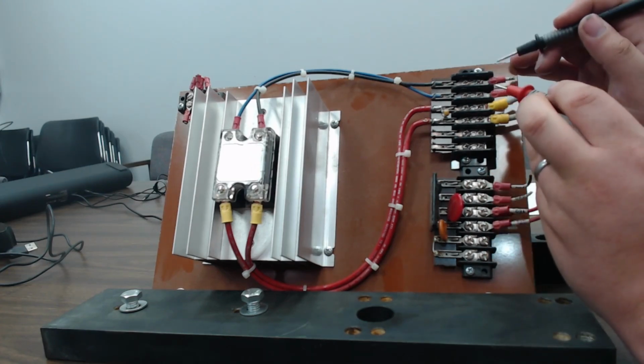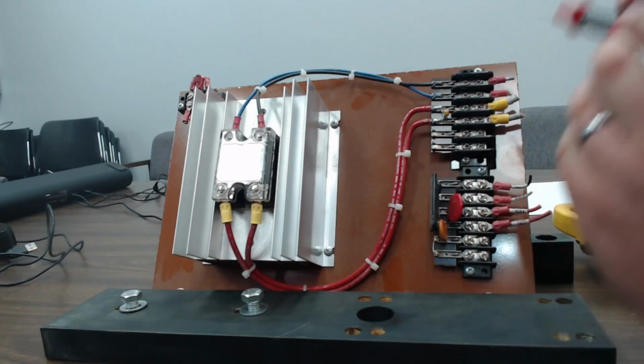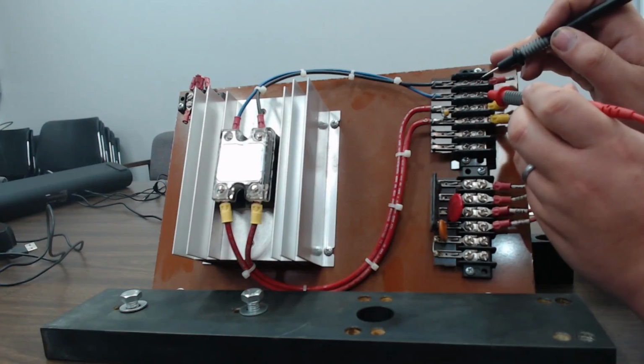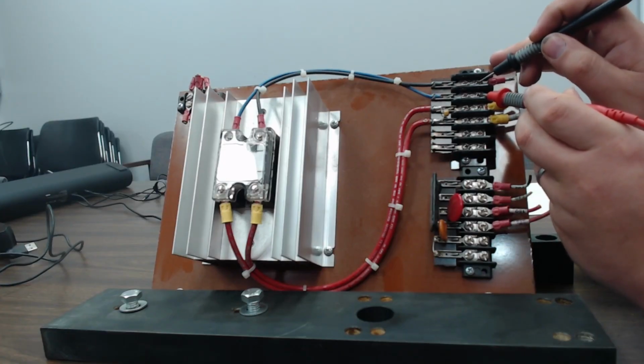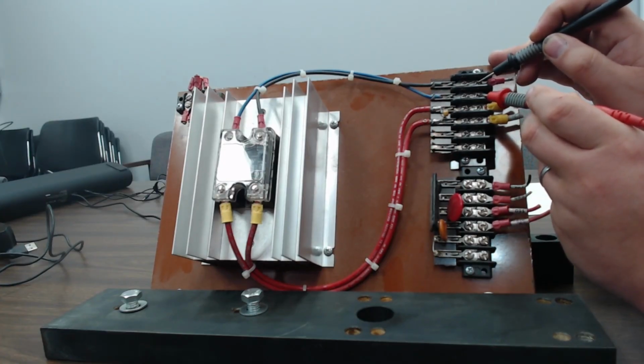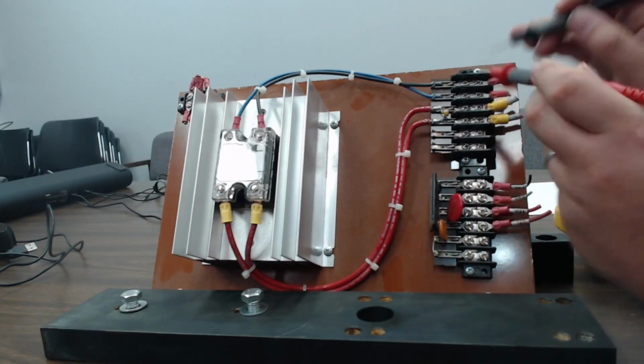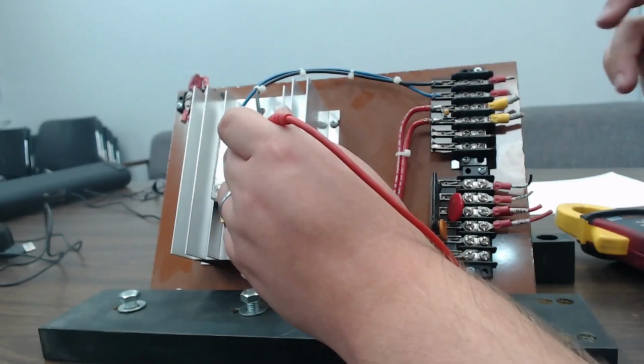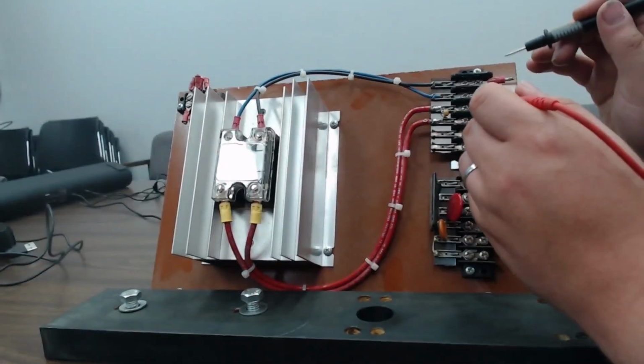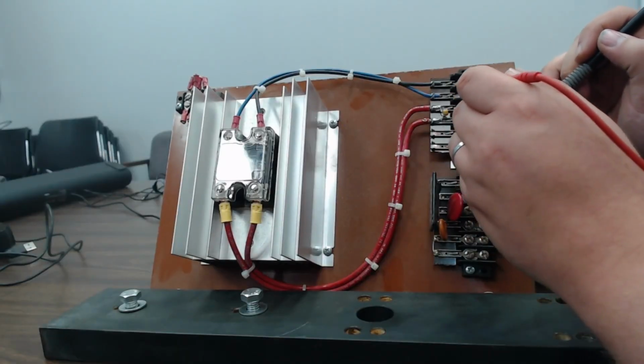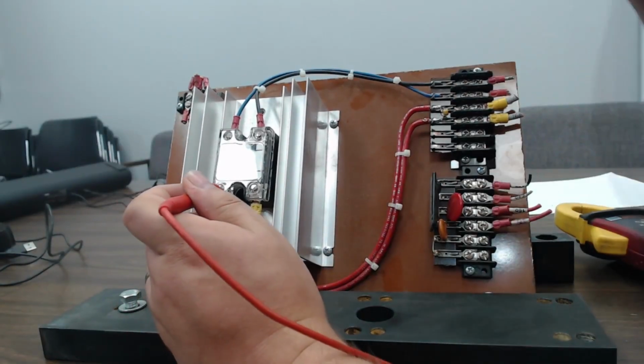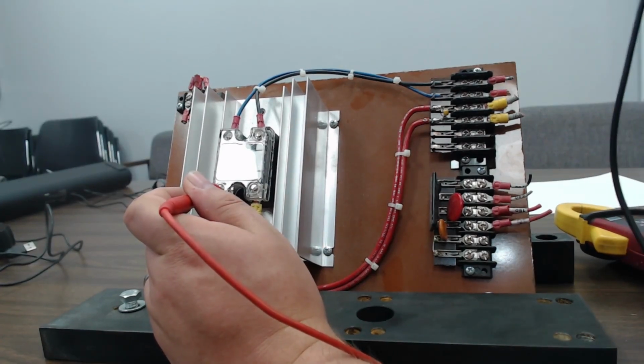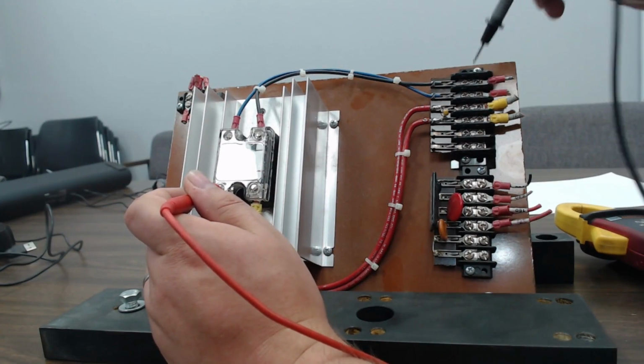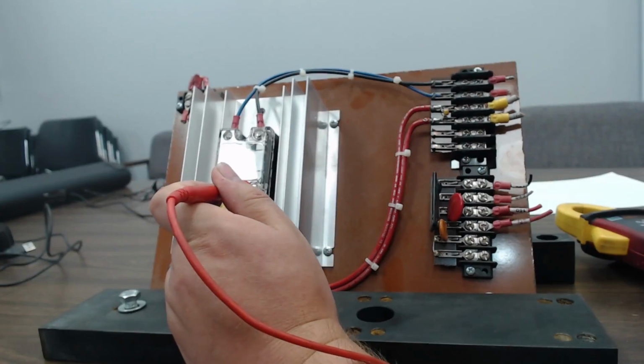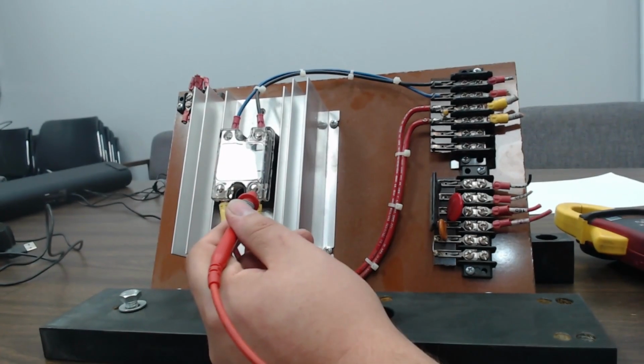On the ramping up, ramping down circuit, same thing, 0 to 3 volts DC. You're looking to see as it scales, as you hold that up arrow, it's going to linearly increase. You can check it here as well. You're making sure you don't have a bad solder connection or anything going on. Same thing for here, your big wires. The 250 should always have the neutral in, and it's going to be 120 all the time.